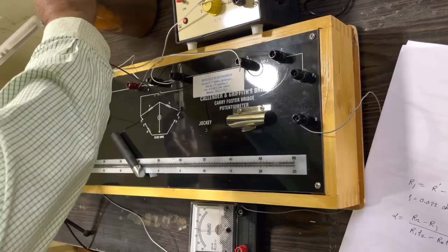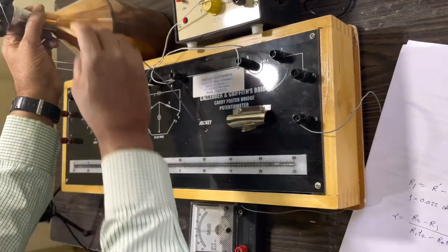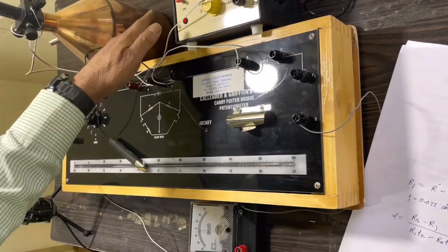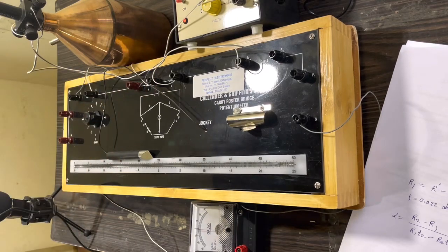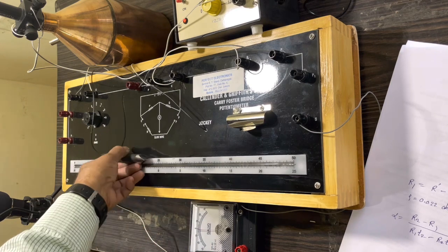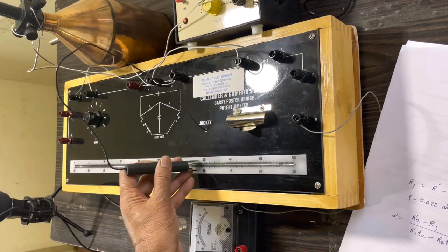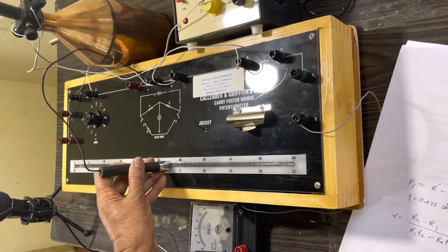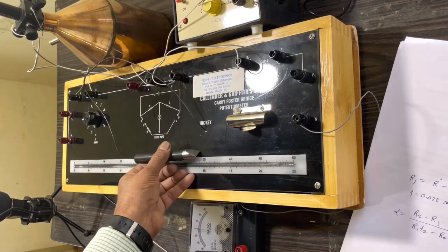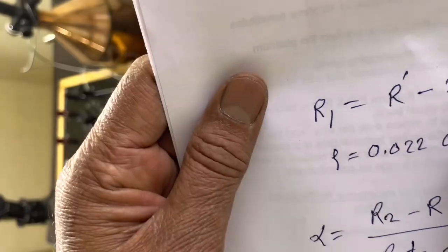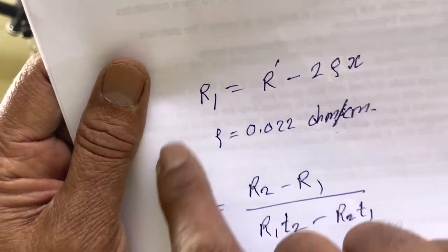You insert the platinum resistance thermometer inside the steam chamber. Add 50 percent water in the steam chamber and heat it to boil the water, so that the temperature of the boiled water will be 100 degrees Celsius. Then we have to obtain the balance point for the temperature of 100 degrees centigrade.